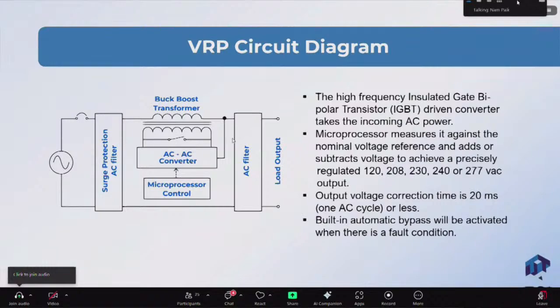So once we have regulated voltage coming out of this buck boost transformer, and we do this on a half cycle by half cycle or cycle by cycle basis, we detect one cycle of AC, which is 20 milliseconds. Microprocessor sees it and feeds it back and says, okay, the previous cycle, one cycle had a minus 20%. So let's add 20%. So 20 milliseconds later, correct waveform goes out. And this happens 50 or 60 times every second. And that's the power of the microprocessor control, of course.